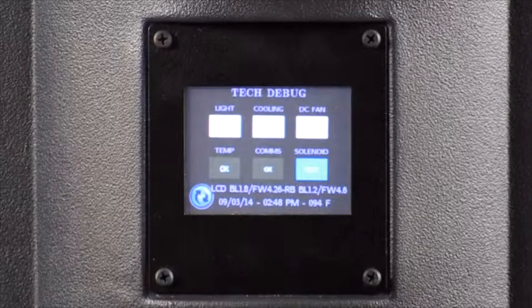This tech debug screen will be displaying multiple items that will be very informative to technicians in regards to being able to test the LED lights, cooling system, and DC fan operation for failure analysis testing. This display will also show that the temp is within the correct operational range as shown by a green square.